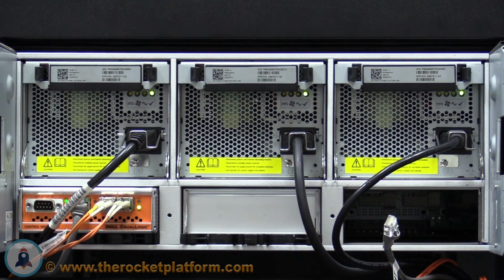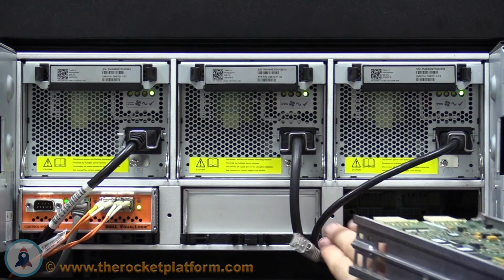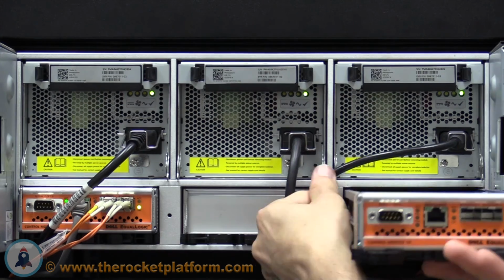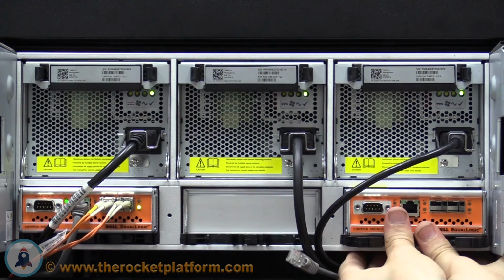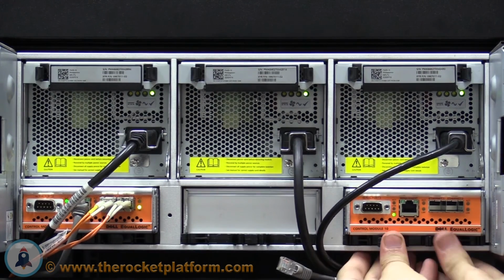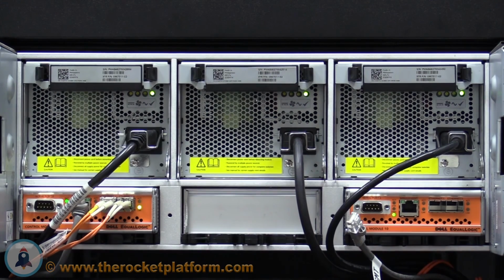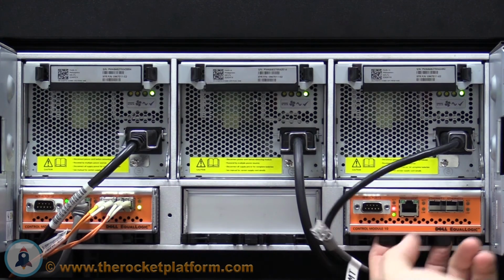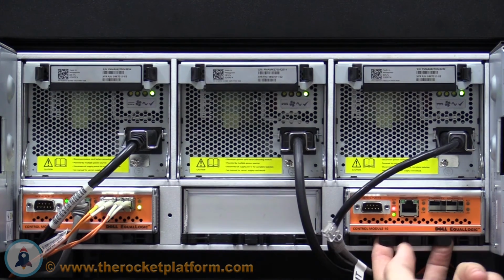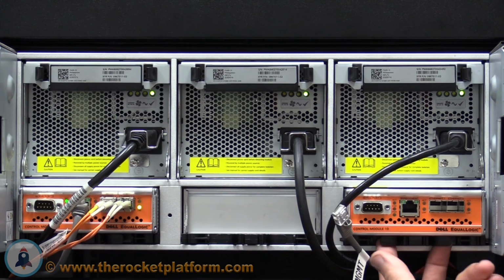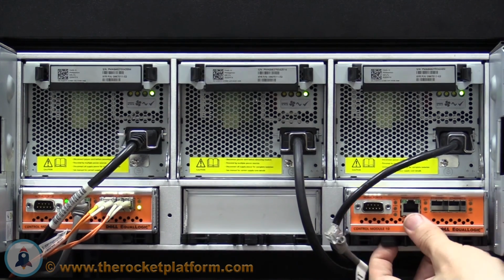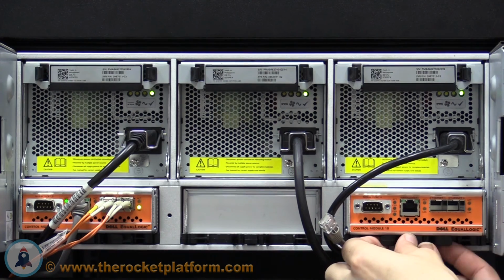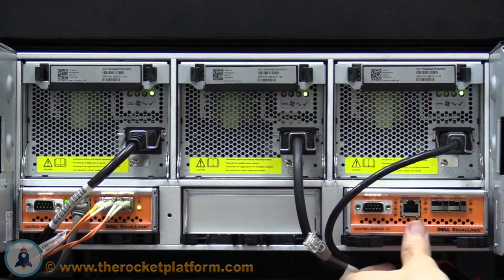Make sure the controller is oriented in the same direction as the controller that was just removed from the said slot. Once seated in around 90% of the way, the black levers should catch in the slots they lock into. Once the levers begin to catch, push the levers shut inwards, which should cause the controller to seat the rest of the way. Grab on one of the levers, making sure not to disturb the tab attached, and pull straight back. If the controller stays in place, then it has been properly seated. If the controller moves around in the slot, then you must reseat the controller until properly seated.